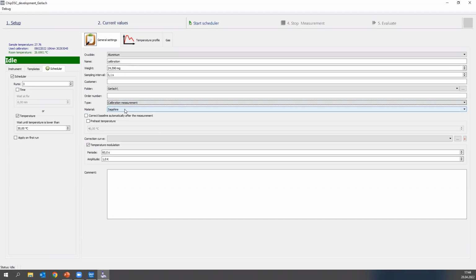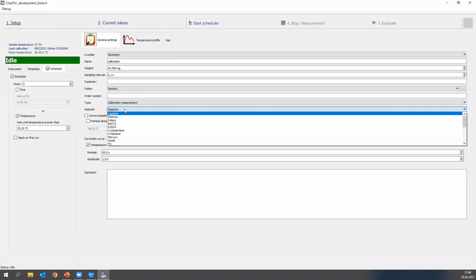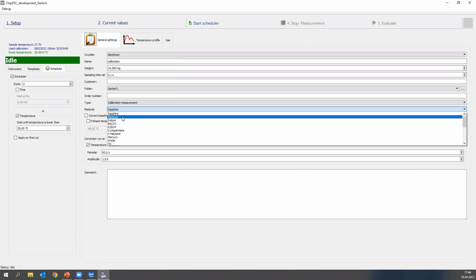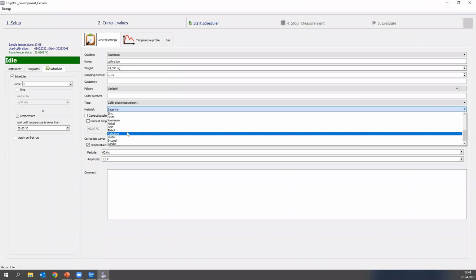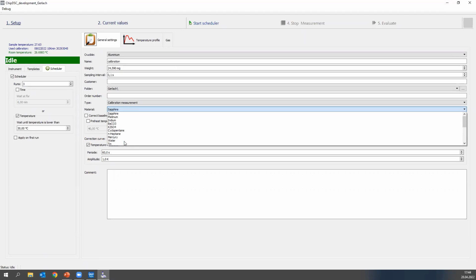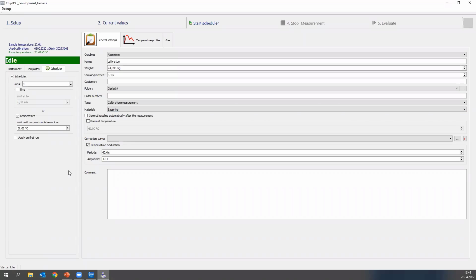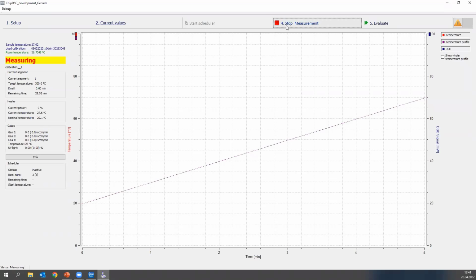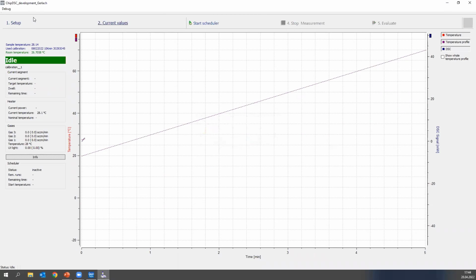Now you can choose the material you want to use. The preset is sapphire, because this is what we normally deliver. But of course, you can use your own material if you have the literature values, or one of our materials from our database here. That's everything we have to change, because temperature profile and temperature modulation must be the same. And so we can go on with the measurement once the correction has stopped.